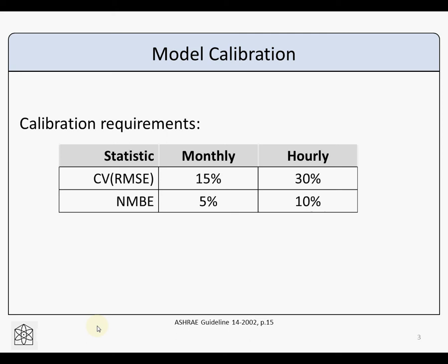So again, be careful with calibration. You sort of have to know what's going on, and if you're getting something like your lighting energy use is 1 kBtu per square foot and your plug loads is 80 kBtu per square foot and it's still calibrating, well, that's great, but you're probably doing something wrong. So just keep that in mind, and that's sort of an issue with EnergyPlus and with these sorts of models which have a whole bunch of input parameters, and the data you're comparing it to is smaller than the parameter input space. That's generally an issue called model overfitting, and you can research that more if you're interested. But just be careful of that with your model and try to make sure that what you're actually predicting still matches some benchmarks.